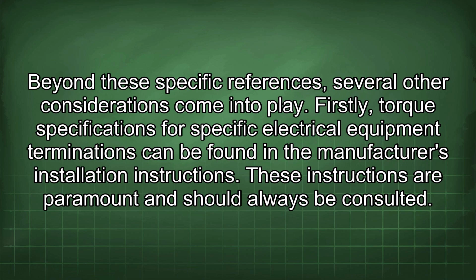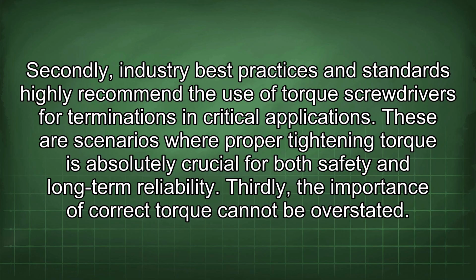Firstly, torque specifications for specific electrical equipment terminations can be found in the manufacturer's installation instructions. These instructions are paramount and should always be consulted. Secondly, industry best practices and standards highly recommend the use of torque screwdrivers for terminations in critical applications. These are scenarios where proper tightening torque is absolutely crucial for both safety and long-term reliability.